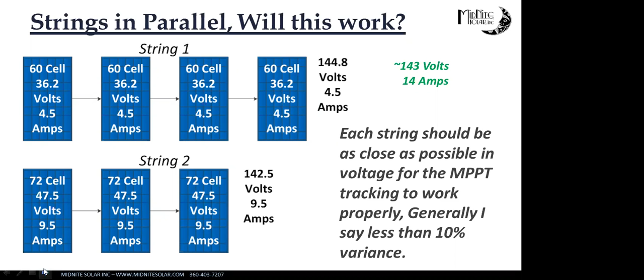If Alti has a deal and they only have 3 of a certain module left, you're like, hey, I don't care, they're going on my barn roof, I can't see them. You can start figuring out how you can make these things work together with a charge controller. The problem is if you start getting these 2 voltages too far apart, when the charge controller does its tracking, it will find both power points, and one of them may be way less efficient than the other. So in this case here, let's say the top array was 140 and the bottom one was 160. It might lock onto the top one and only make the 4 amps, whereas if it locked onto the bottom one, it makes 9 amps. But if you get them close, it'll make the whole 14. So it's just important to get those close, otherwise it will confuse your charge controller.